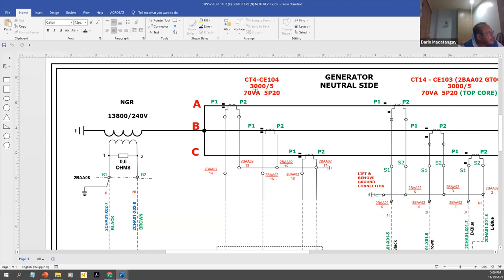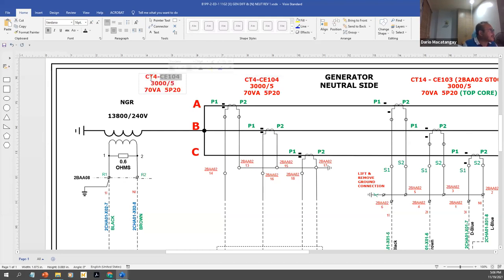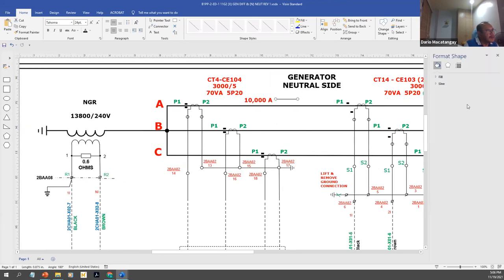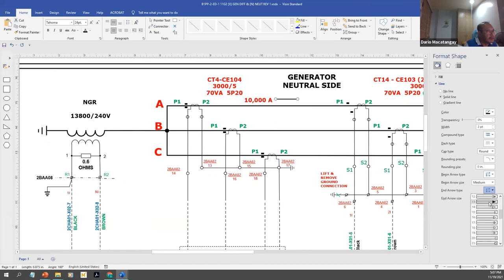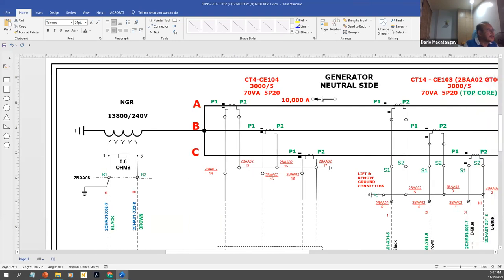So let's say this one is a 3000:5 ratio, right? So what I mean by 3000:5, effectively you have 3000 divided by 5, which is 600, right? So for example, there's a fault current of, let's say, 10,000 amps flowing. So there's a three-phase fault, 10,000 amperes flowing here. So let me see here. So the arrow. Okay, all right, it's going that way, right?